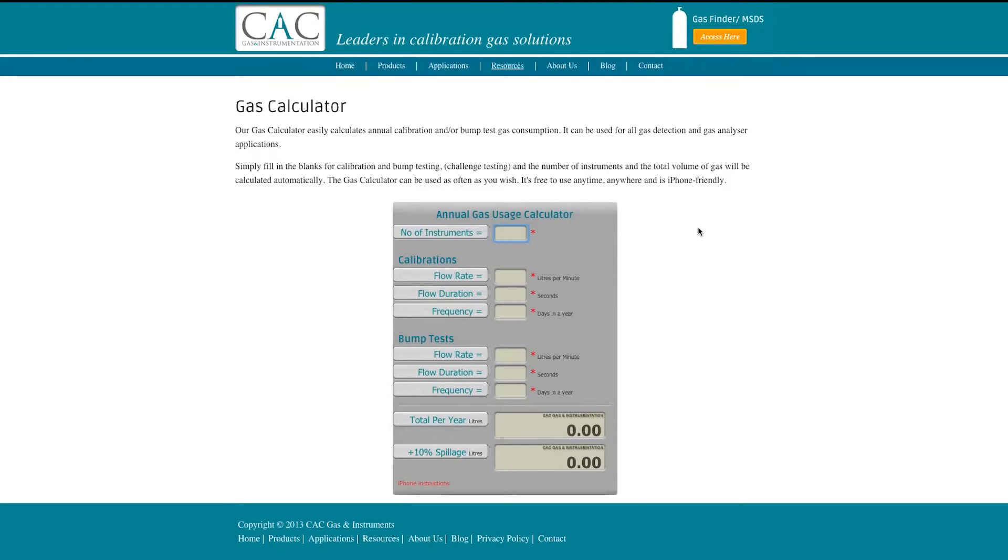Using the CAC gas calculator, simply enter the relevant information in the boxes provided. Enter the number of instruments. For calibrations, enter the flow rate, the duration, and the frequency. For bump tests, also enter the flow rate, the duration and the frequency. The gas calculator will automatically calculate the annual gas usage of the customer.